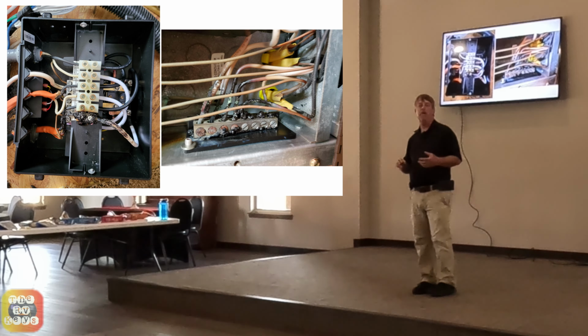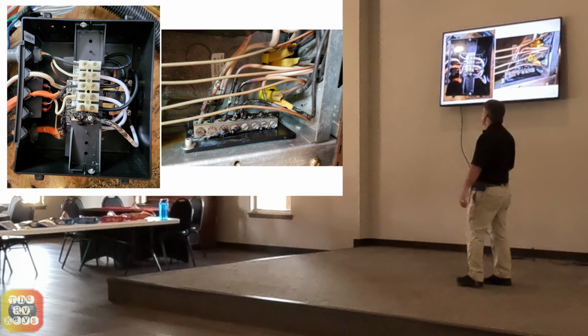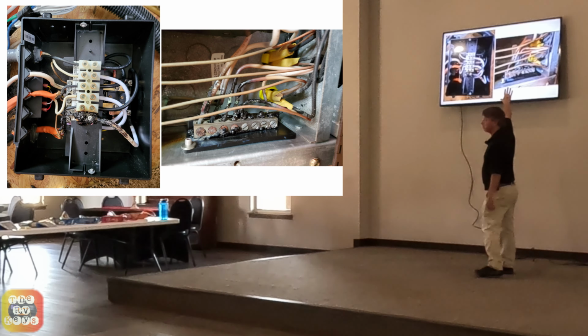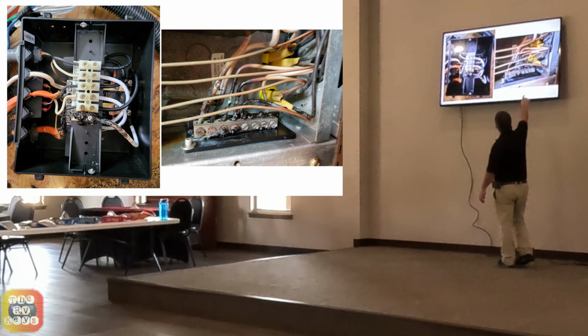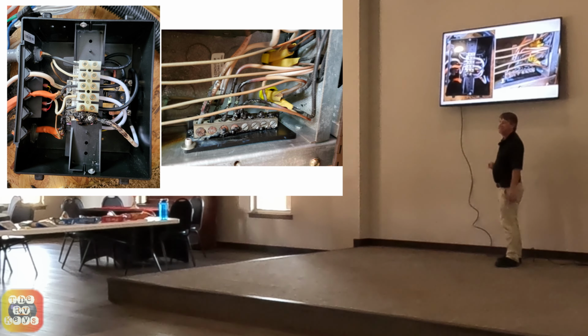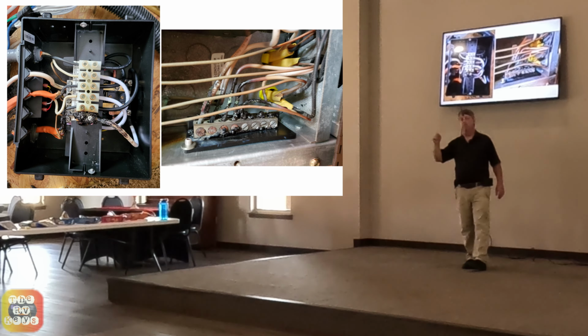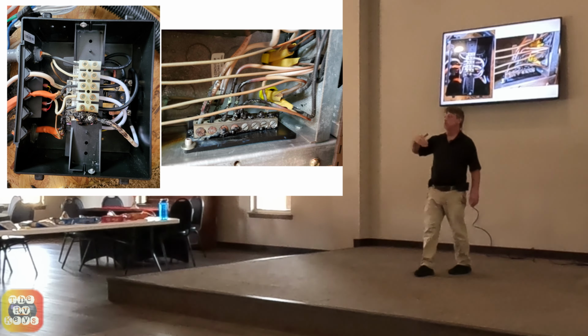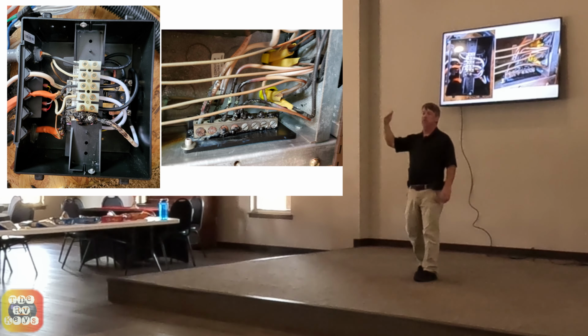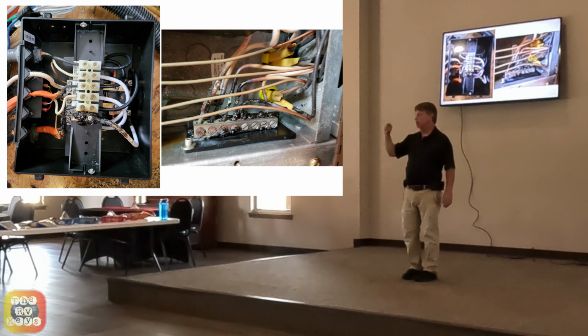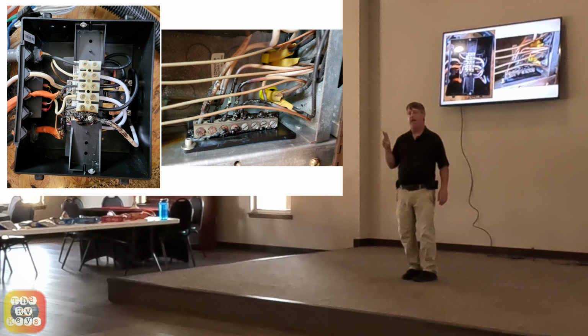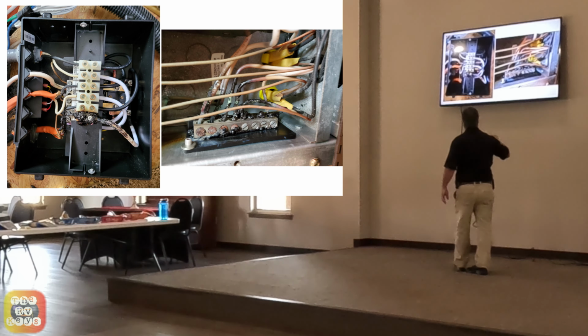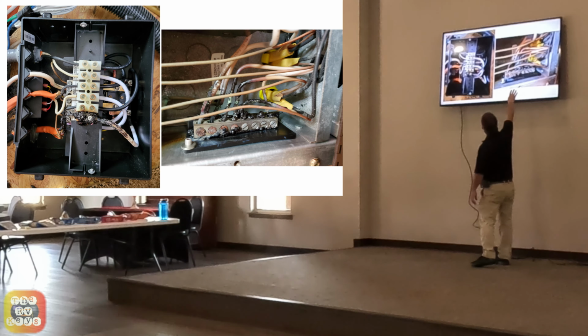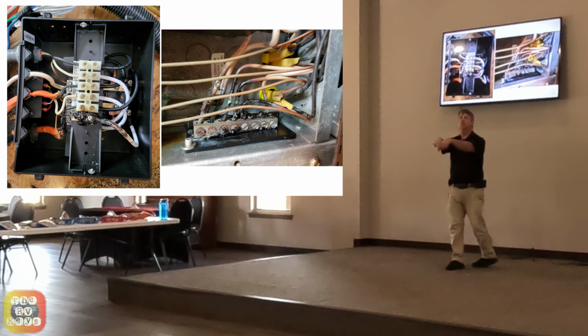One of your checklist items every year should be to have a qualified person open up your circuit panel and check that all of these lugs are tight. Over time, the wires will heat up, they will cool down, they will expand, they will contract, those screws will loosen. RV manufacturers don't help this because every once in a while, and I don't know if it happened here, every once in a while they'll put 2 wires into a single spot.